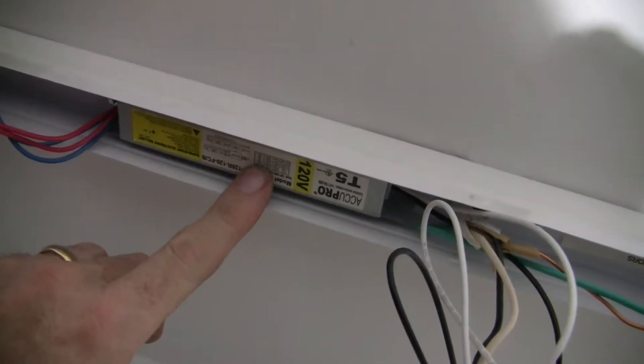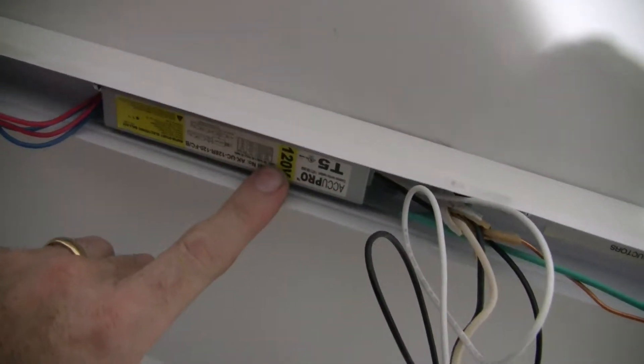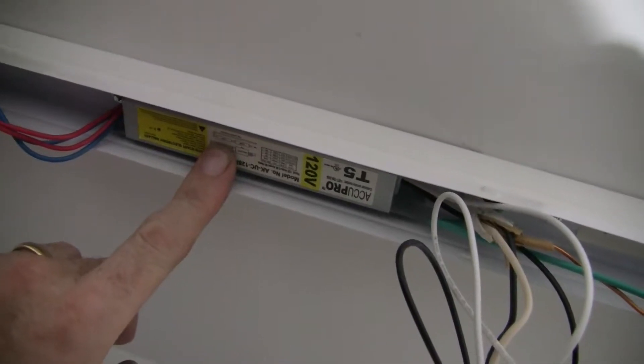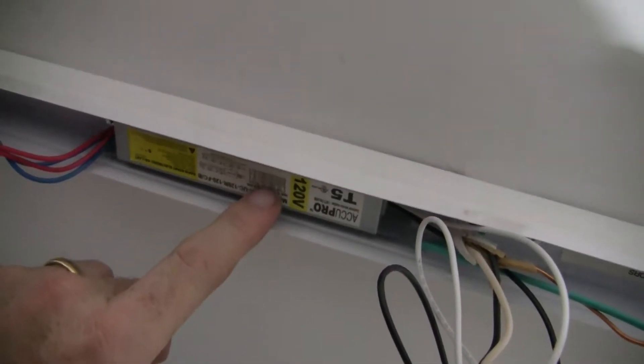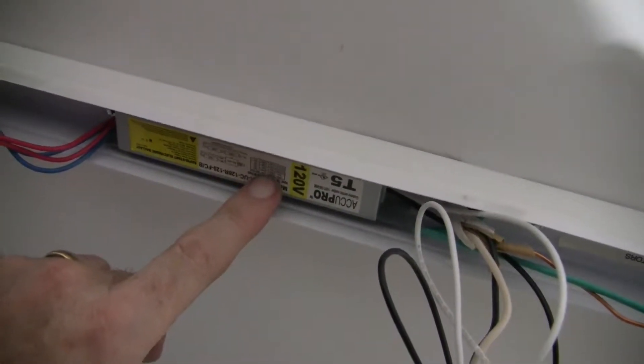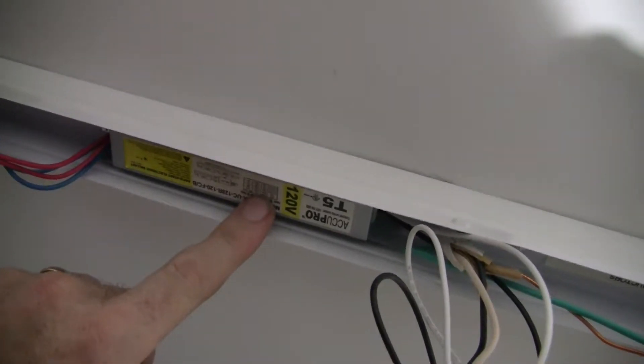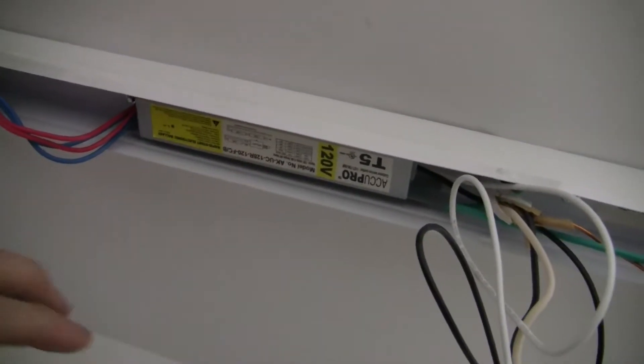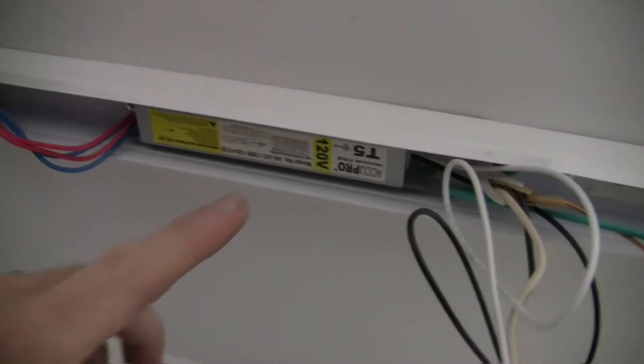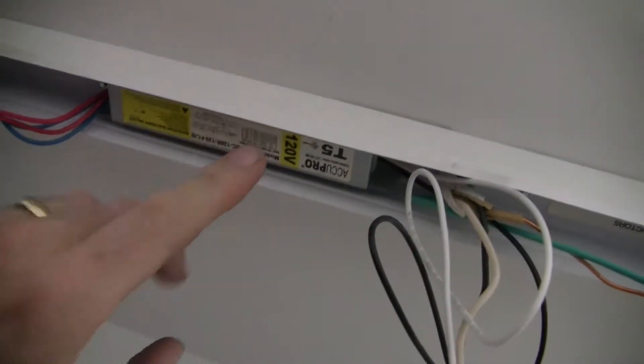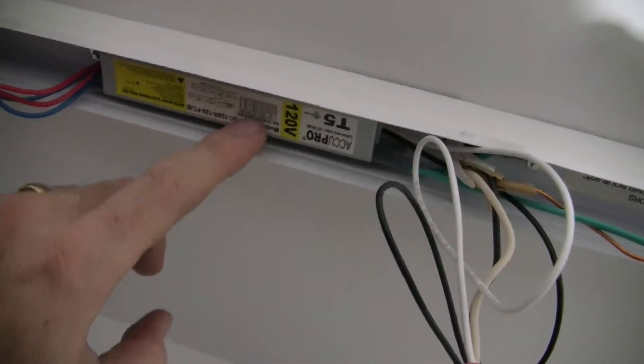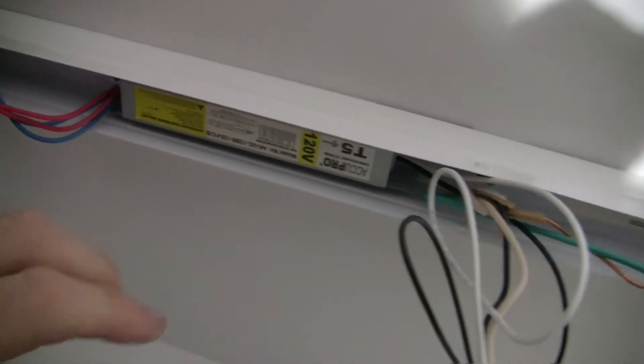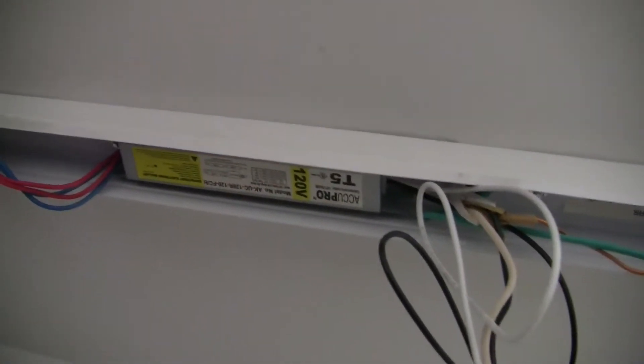Make sure you get a ballast that exactly matches voltage and the wattage and the lights that it can handle. And the wattage of the lights that it can handle and how many it can handle and how it's wired. Those are the important things to look at. Make sure you get the exact same ballast. It can be from a different company, but it's got to have the same standards and the same wattage and cover the same number of lights.